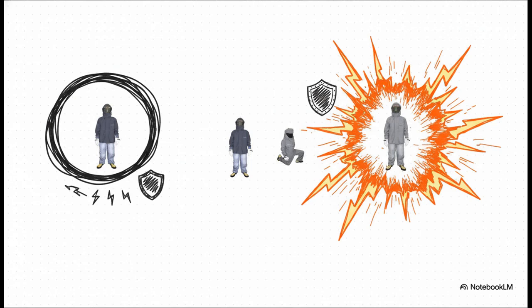Okay, so let's put some visuals to those numbers. On the left, that's your Category 2 gear, rated for at least 8 calories. Now look at the right - that's Category 4, for a minimum of 40 calories. The difference is pretty stark, isn't it? You go from basically a heavy-duty shirt, pants, and a face shield to a full-blown multi-layer flash suit. The protection scales right along with the danger.